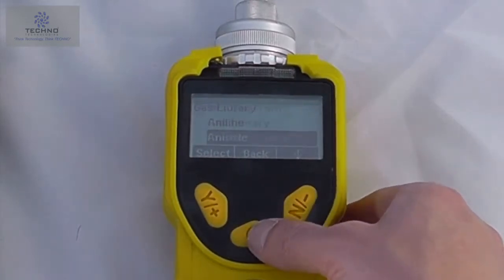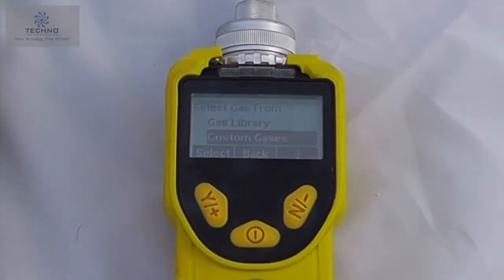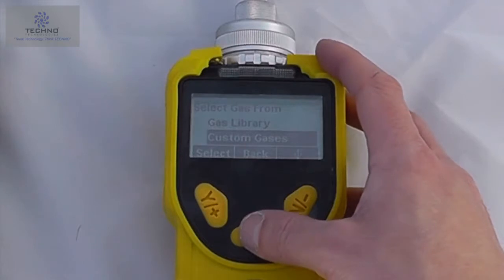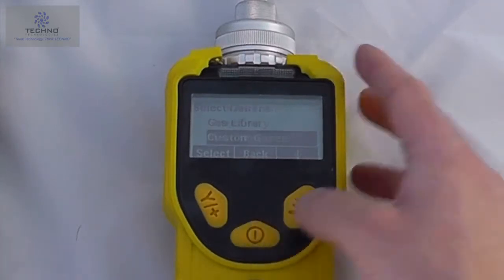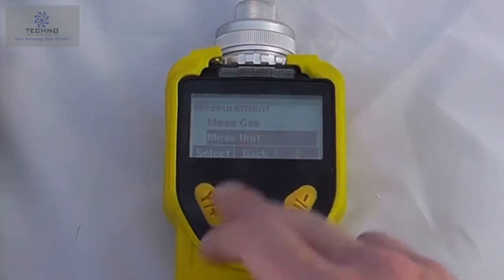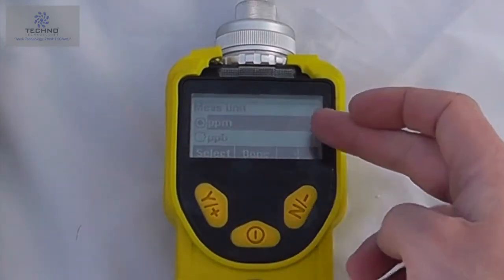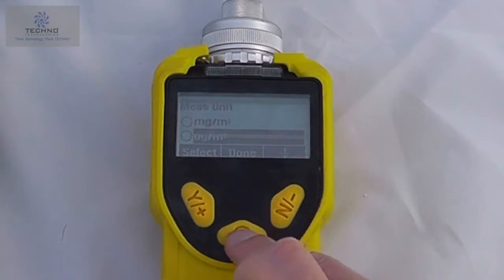And if I go back, we can also do some custom gas settings. So dependent on if you have a standard gas calibration mix, you may want to do a custom gas correction factor. If we just now go back, we can also look at our measurement units, be they parts per million or milligrams per cubic meter or micrograms per cubic meter.